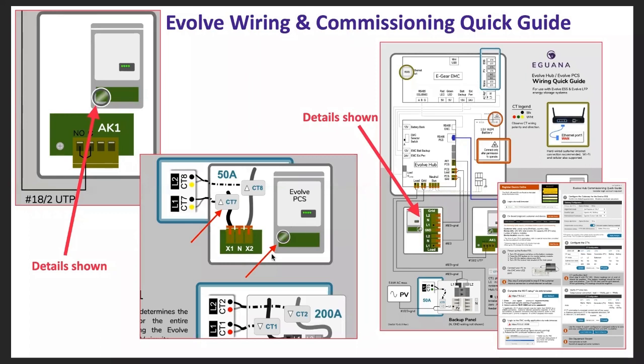For example, what these arrows are pointing to are inside the PCS cabinet. This is the PCS cabinet because it's got the lights on it. The detail has a little circle, and inside that circle shows where these conductors are that you would then place the CTs onto. The triangles show the arrows noting the direction that the CTs need to be oriented, as an example there.